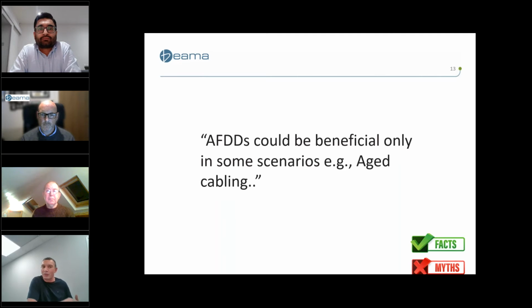Plugs and sockets over a period of time, as you insert and pull out, can become worn. I've certainly had an occasion here in the factory where overloading of a plug and socket over a long period with a fan heater caused a burnout on the neutral pin, detectable by an arc fault detector. It caused charring and a breakdown in insulation. So it's a good solution for retrofitting as much as new builds. Anybody else want to add to that one?